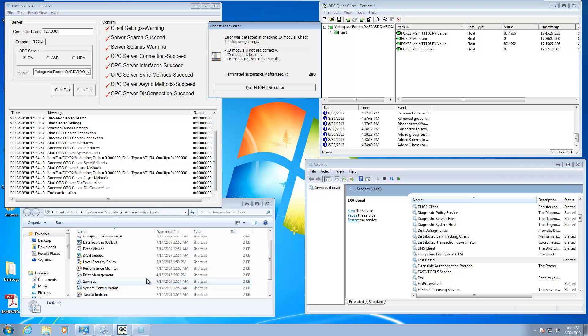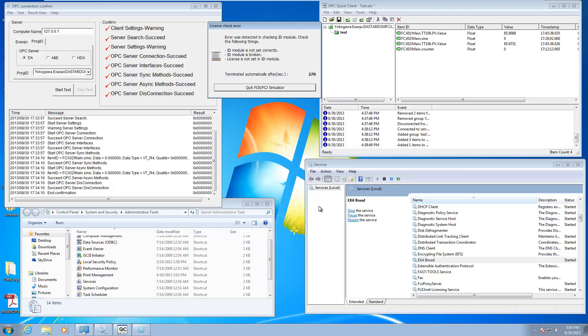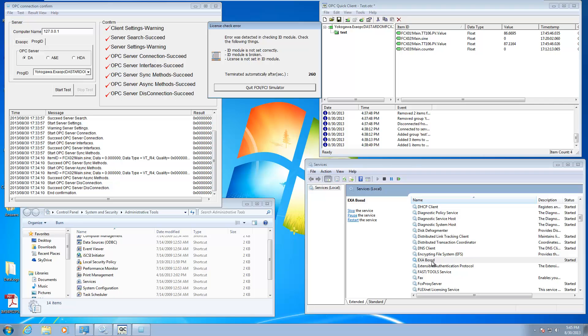Say you've gone in and edited the CSV file and added a couple new Stardom units to your system. Instead of the recommended reboot that it says in the instruction manual, you can actually go into your control panel, go to systems and security, administrative tools, and go ahead and open up your services. There's a service called ExaBossD. If you stop this and then restart it, it'll load in those configuration files. So that'll kind of stop your OPC connection, load in the new IP addresses, and then you should be good to go.